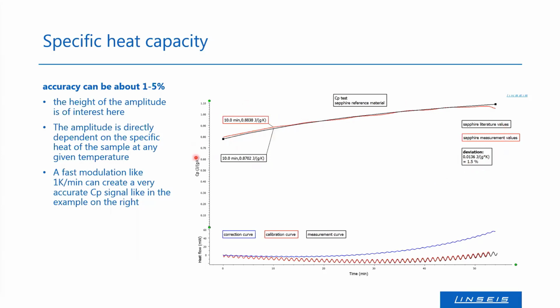What's important is that at the very beginning of the measurement and at the end, the values could differ from the literature, because you need a complete modulation to receive good signals, because you have to evaluate the amplitude, as I mentioned before. What you can see here at the bottom is our correction curve, the calibration curve, and of course the measurement curve.